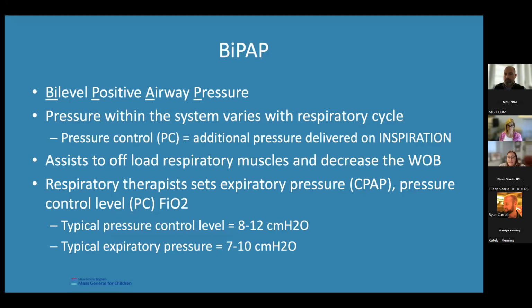So in this instance, we'll set the expiratory pressure, or the CPAP, and the pressure control level, and again, the FiO2. I will say this can be rather confusing because there's different nomenclature for some of these parameters. CPAP can be referred to as EPAP. You can set the pressure control, pressure support level, and the two combined then get you the peak inspiratory pressure and or the IPAP that's delivered to the patient. Again, it depends upon the device that you're using. So it's helpful to work with the respiratory therapist so that you understand the support that the patient's receiving.